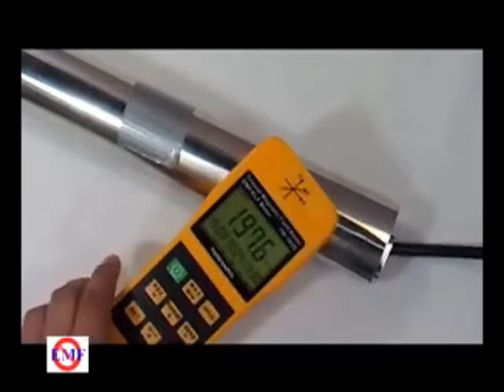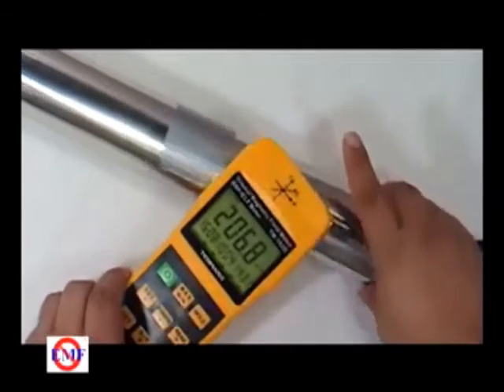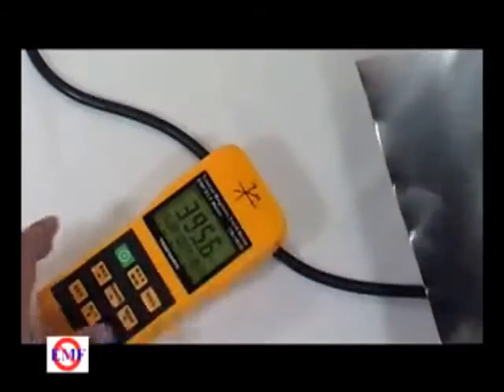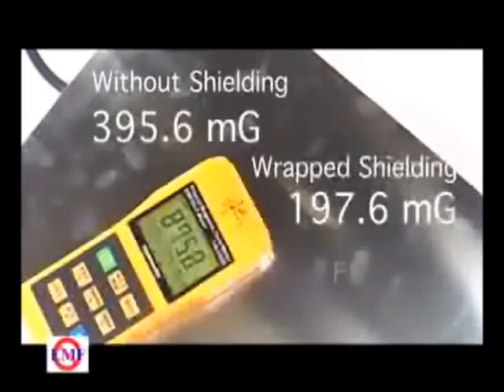Shielding net current is done with flat plates of magnetic shielding material. These fields should not be shielded by wrapping the wires as it will have little effect. Flat shields help contain the field in the area of the shield.